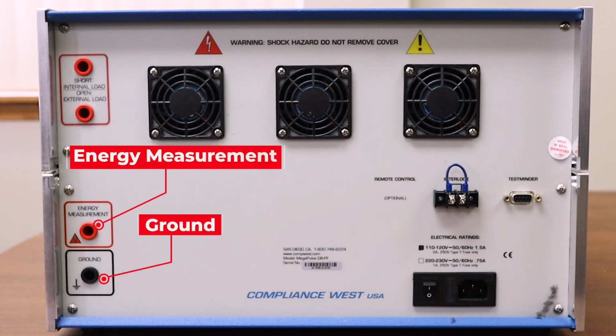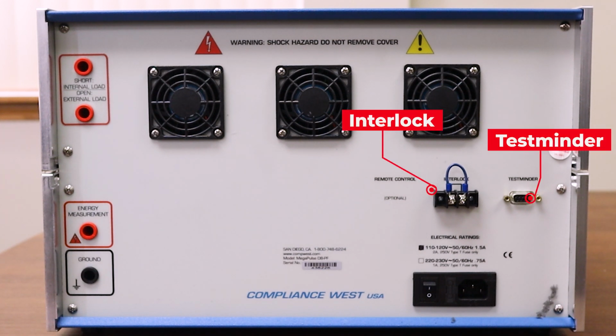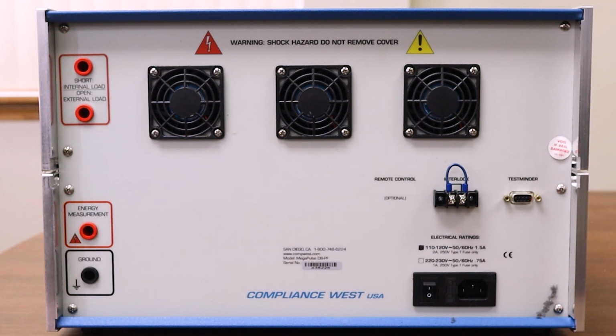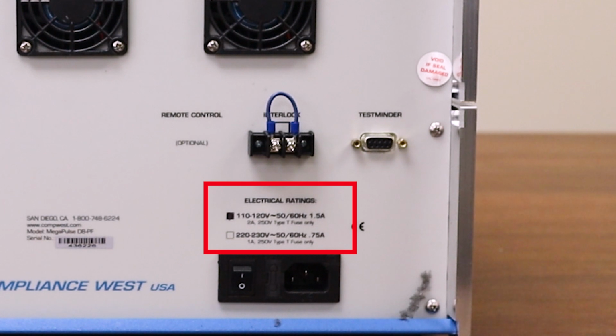If these aren't being used, there needs to be a jumper placed across them. Below that, in the lower left-hand corner, we have our energy measurement and ground connections. As we work our way towards the right side, we have the interlock and test minder, and then below that we have our AC input. As you can see, we have the 110 to 120 volt option as indicated there. Below that you can see the other voltage option, 220 to 230 volts, which can be ordered as well.